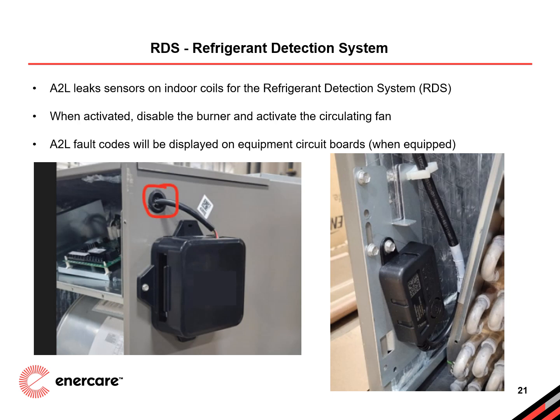Additionally, a fault code display. Most systems interface with the equipment's control boards to display specific A2L fault codes, aiding technicians in efficient troubleshooting and maintenance. It is important to note that while the overall design philosophy of RDS is not standardized across all manufacturers and configurations, design and implementations will vary.